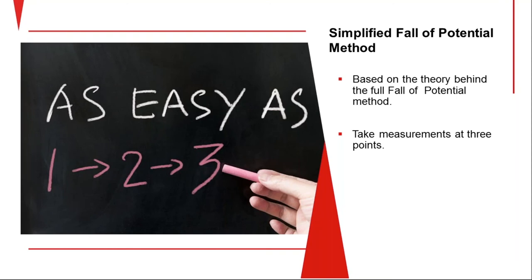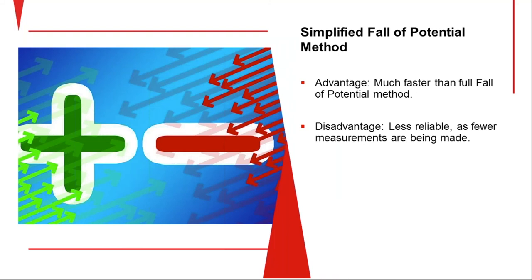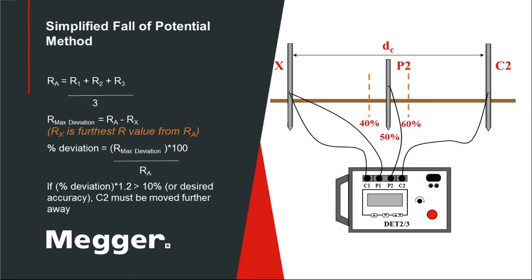Simplified fall of potential is the same idea made a lot quicker. We're running out of time, so I won't go into detail. Basically you're using fewer measurements, only going to measure three points: half the distance and then 10 percent in and 10 percent out of the distance to your current probe. There's a little mathematical crunch you put those numbers through. What that tells you is your percent accuracy. If you've got two and a half ohms at your 50 percent position and a two percent accuracy, you'd be pretty happy.